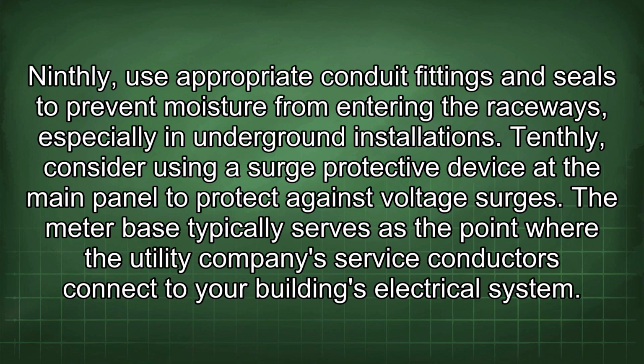Ninthly, use appropriate conduit fittings and seals to prevent moisture from entering the raceways, especially in underground installations. Tenthly, consider using a surge protective device at the main panel to protect against voltage surges.